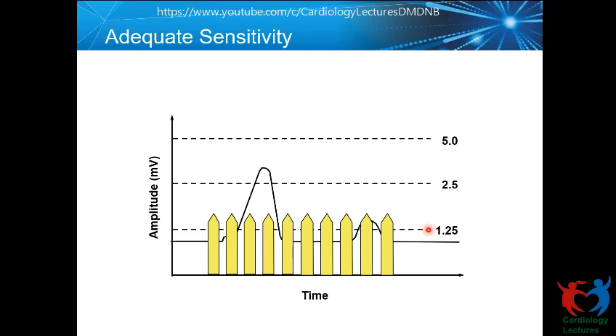Similarly, the R waves also. The normal setting is 2.5 and your R wave is 5 or 8, so we don't have a problem. But if the R wave is dropping, like what was explained earlier, then we really have to look into sensitivity, whether we're going to miss any low voltage R waves. But at the same time, we can't reduce the sensitivity to a very low level because you'll be oversensing a lot of other things and in turn get inhibited. Okay, sir.